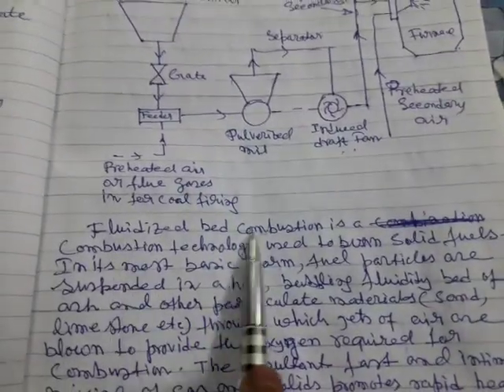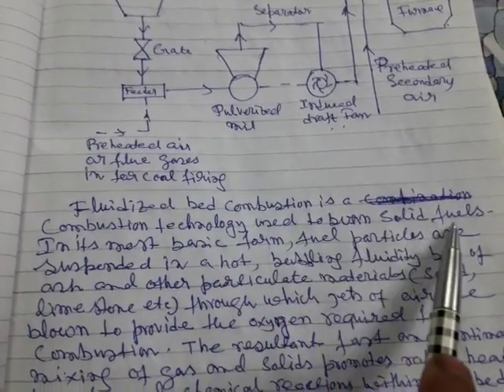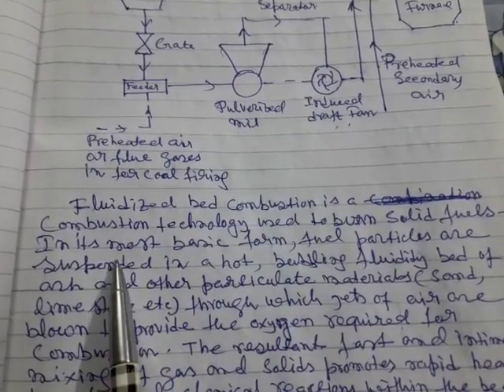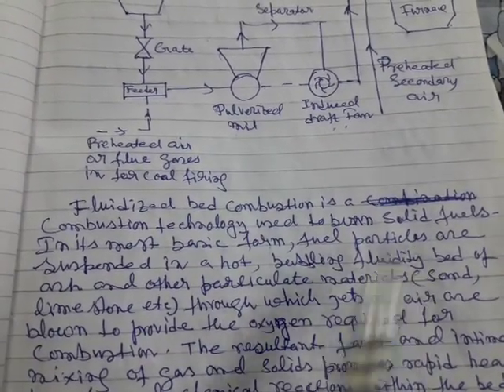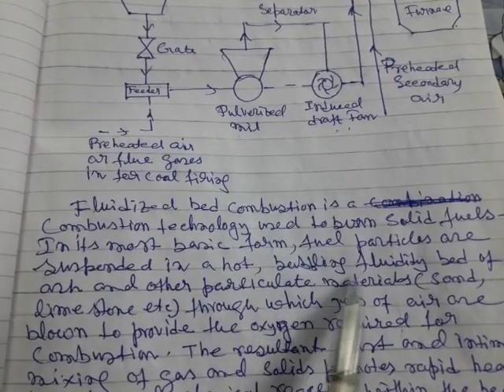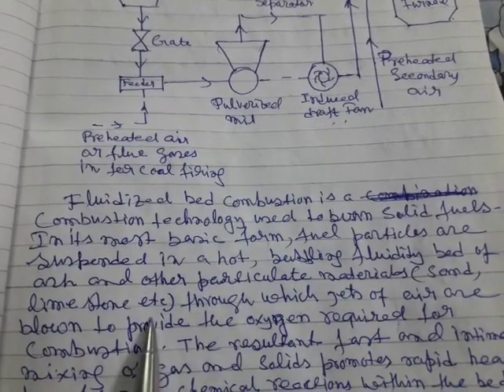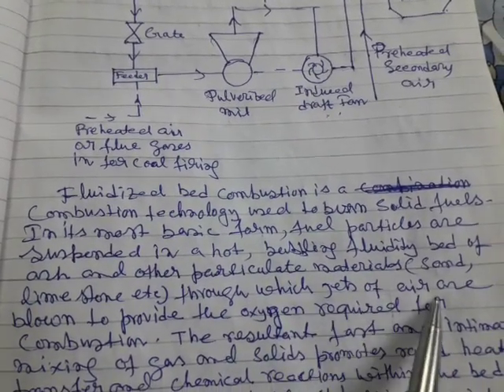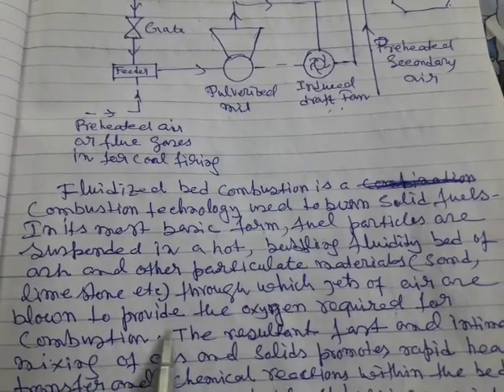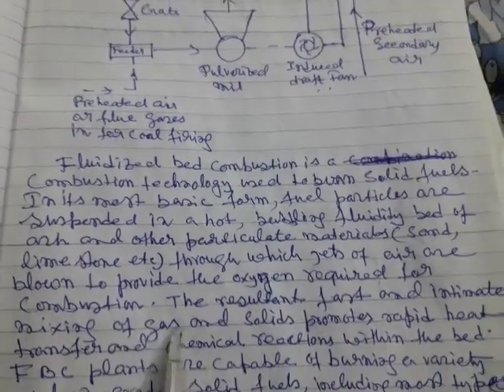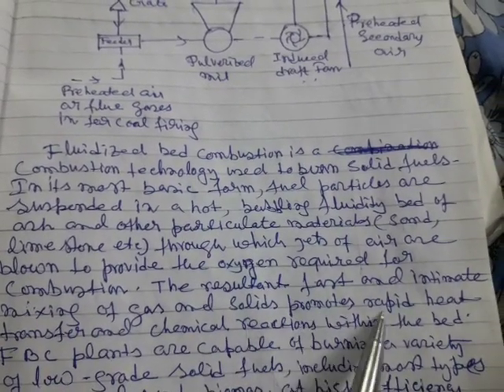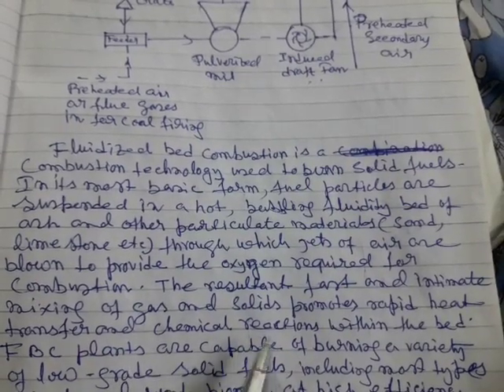Fluidized bed combustion (FBC) is a combustion technology used to burn solid fuels. In its most basic form, fuel particles are suspended in a hot bubbling fluidized bed of ash and other particulate materials like sand and limestone, through which jets of air are blown to provide the oxygen required for combustion. The fast and intimate mixing of gas and solid promotes rapid heat transfer and chemical reaction within the bed.